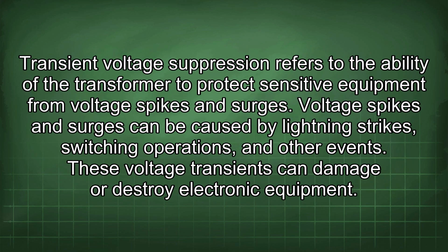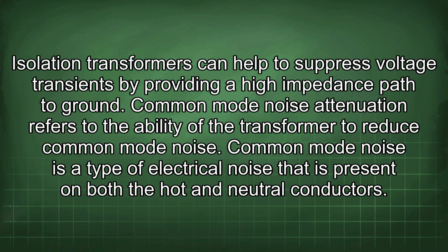Transient voltage suppression refers to the ability of the transformer to protect sensitive equipment from voltage spikes and surges. Voltage spikes and surges can be caused by lightning strikes, switching operations, and other events. These voltage transients can damage or destroy electronic equipment. Isolation transformers can help to suppress voltage transients by providing a high impedance path to ground.